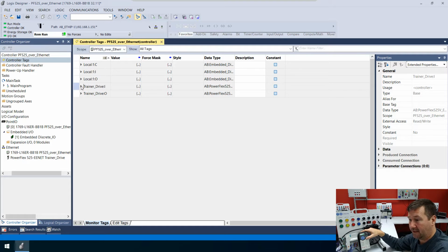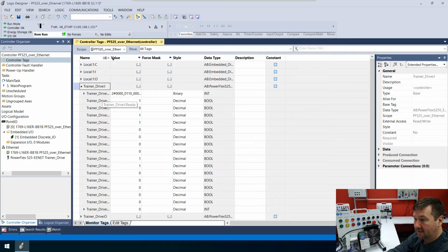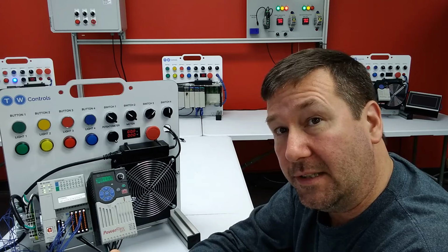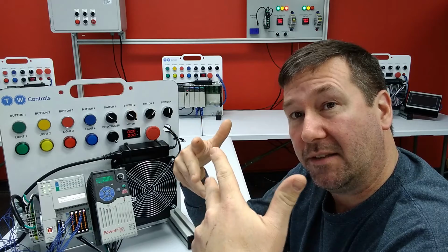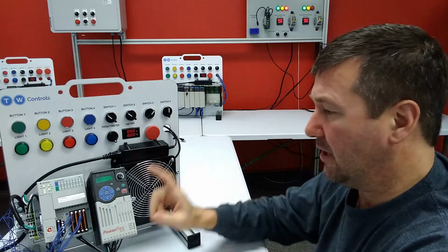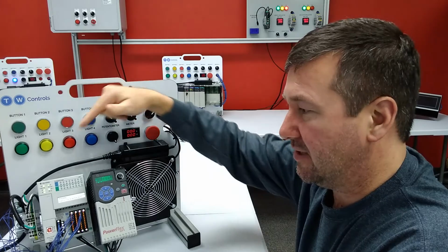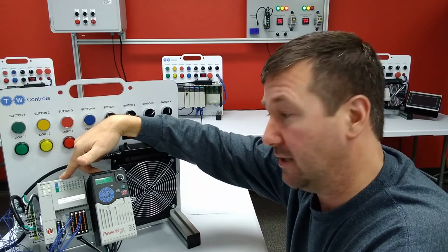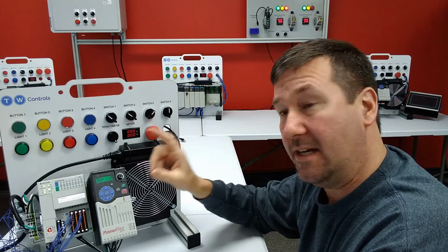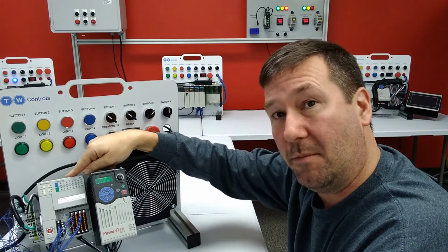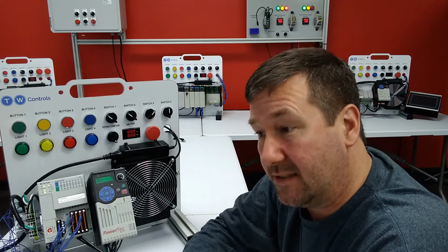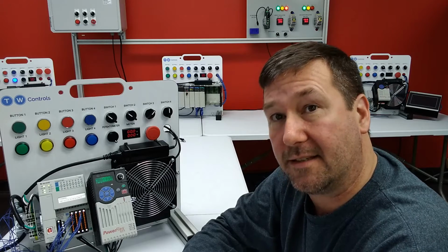And even right now without it running, let's open up our inputs and we can see we have some data in here. Are we looking for inputs or outputs? When it comes to inputs and outputs, it can get really confusing when you're talking about things that are communicating between each other, because the drive will output something to a PLC input. The drive will read with an input something from a PLC output. So you have to think about where your perspective is. And this is Studio 5000, and we are looking at this CompactLogix PLC. So its perspective is here.